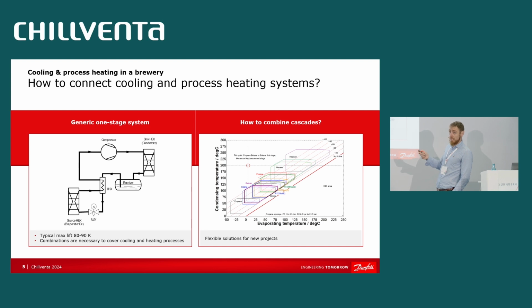And we show the envelopes of the compressor from very low temperatures with some hydrocarbons like propane. You can do refrigeration down to minus 25. If even lower is needed, you can have subcritical CO2, even lower. And in theory, you can have evaporation of hydrocarbons, or rather condensing, up to 200 C. Now, if that is realistic or at all needed, that's another question.